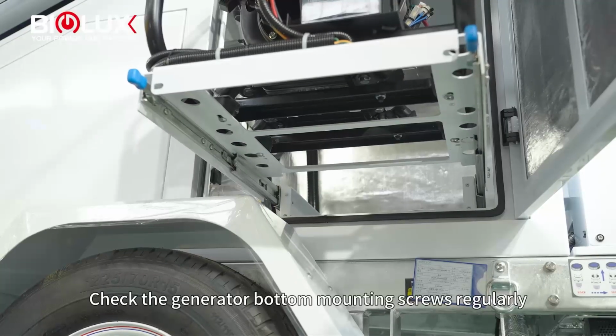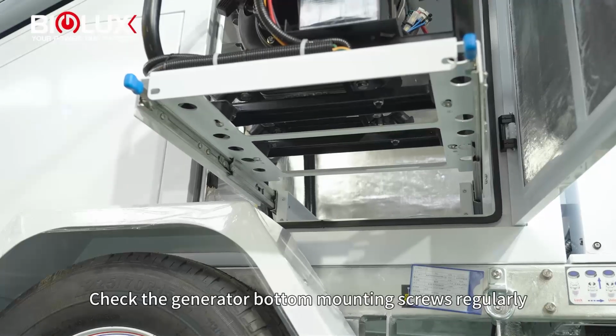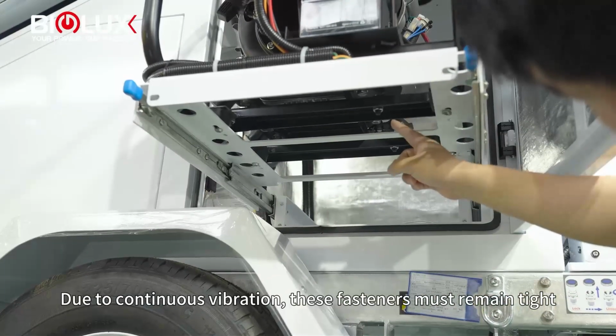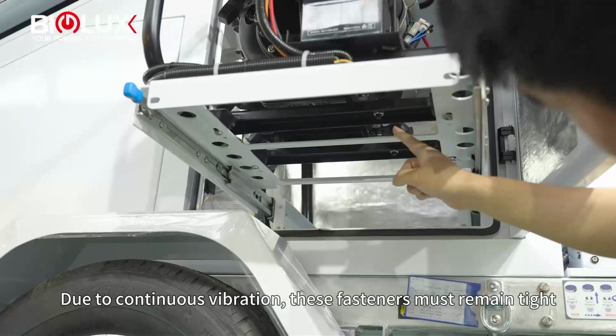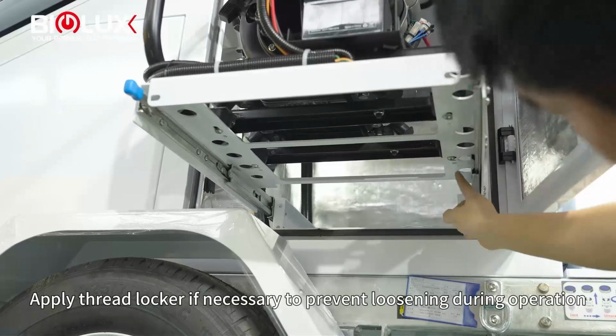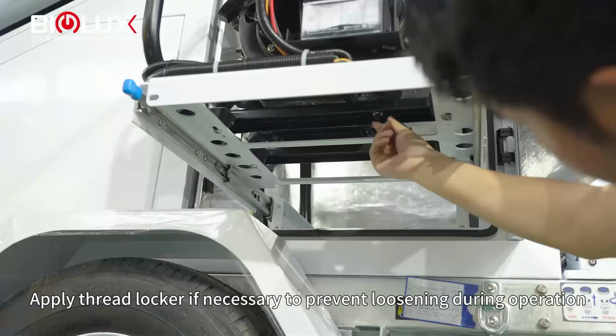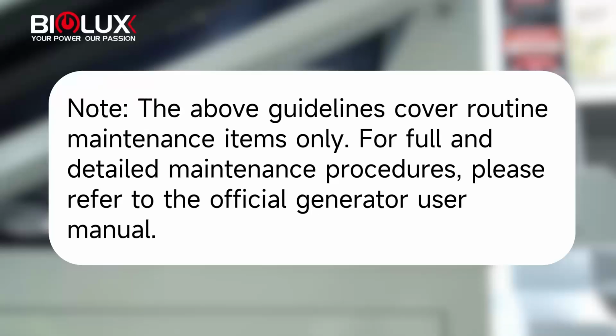Check the generator bottom mounting screws regularly. Due to continuous vibration, these fasteners must remain tight. Apply thread locker if necessary to prevent loosening during operation. Note: the above guidelines cover routine maintenance items only. For full and detailed maintenance procedures, please refer to the official generator user manual.